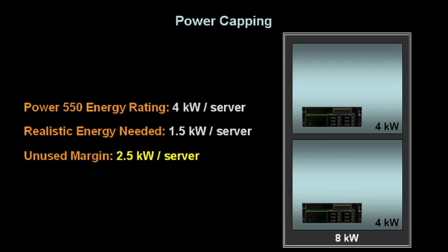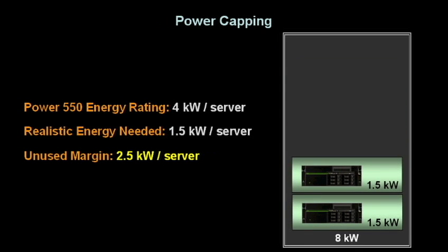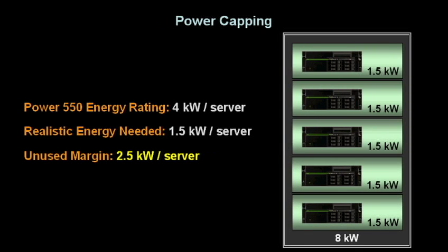The power capping feature lets us reclaim this margin. Through the AEM interface, we can ask the system to guarantee that it will never use more than a set amount of power. If we cap our 550s at 1.5 kilowatts, we'll now be able to add three more servers to our rack. This more than doubles our capacity and significantly conserves space in the data center.